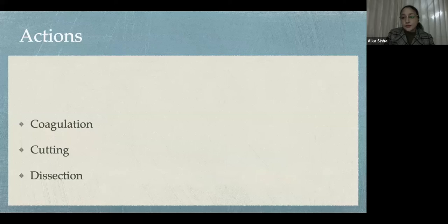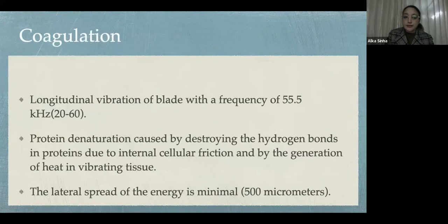The actions of these shears are cutting, coagulation, and dissection. Let's understand how each occurs. There's a longitudinal vibration of the active blade with a frequency between 20 to 60 kilohertz. The harmonic, for example, is 55 kilohertz. Due to this vibration, there's protein denaturation caused by destroying the hydrogen bonds in the proteins, due to internal cellular friction and the generation of heat in the vibrating tissue. During coagulation, the lateral spread of energy by these devices is very minimal.